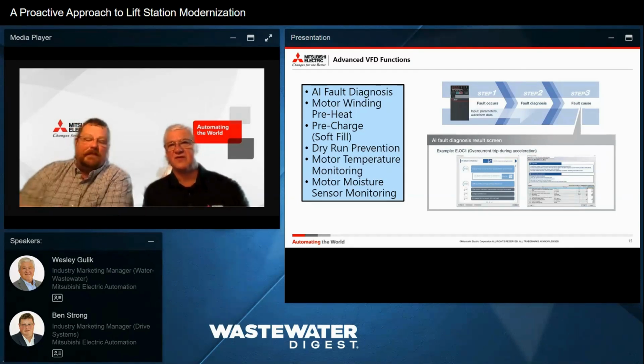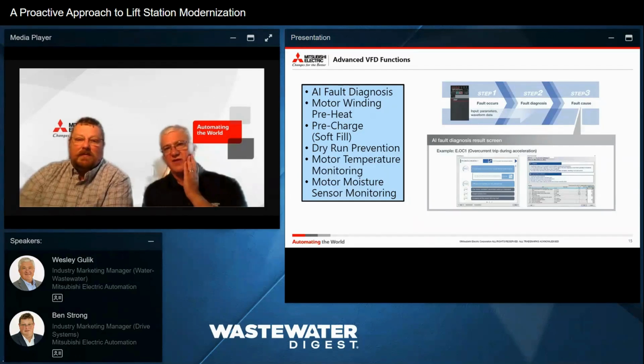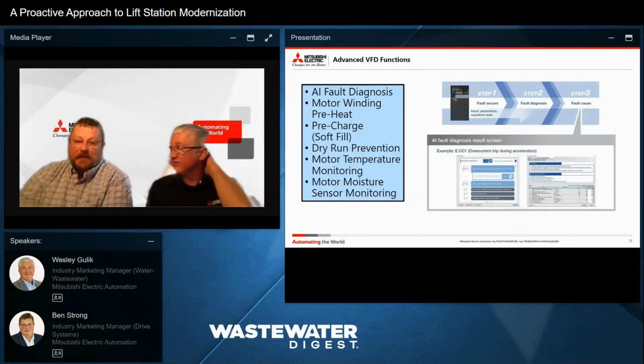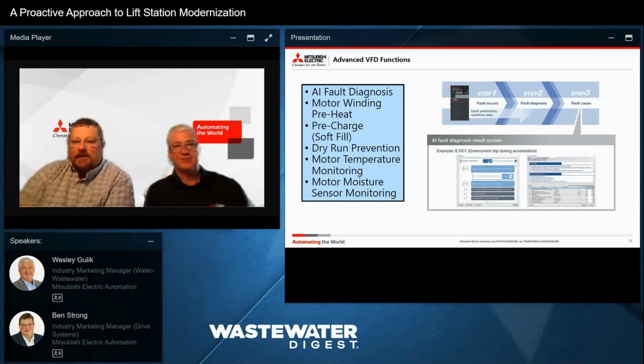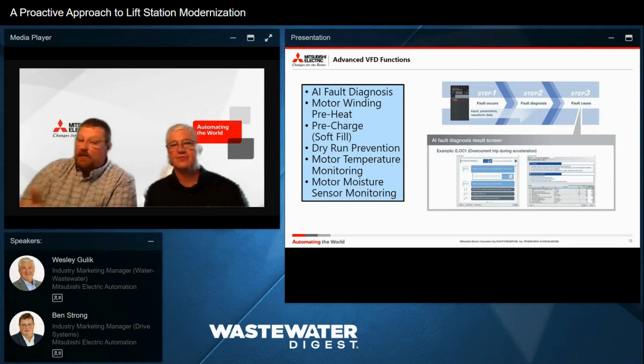So it looks like the VFDs, as we said earlier in the presentation, are becoming smarter and smarter with a lot of these advanced VFD functions. But I'm also hearing that with the latest releases, they may have component monitoring on the variable frequency drive. So I think that's taking it to the next level: hey, your fan is approaching a 10-year life cycle. You've cycled your capacitors to the design life, right? A lot of manufacturers design their drives for a 10-year life cycle on their capacitors. And that also is a number of energized cycles. So the drive will count those and say, look, these capacitors are, I hate to say wonky, but at the end of life, maybe they last another 5 years, maybe they go.